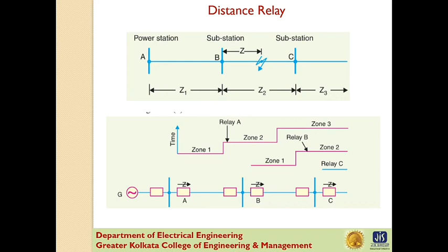The zone 2 element trips for faults in the remaining 10% of the line and faults in the next line section. But a time delay is introduced to prevent the line from being tripped if the fault is in the next section. The zone 3 element provides backup protection in the event a fault in the next section is not cleared by its breaker.